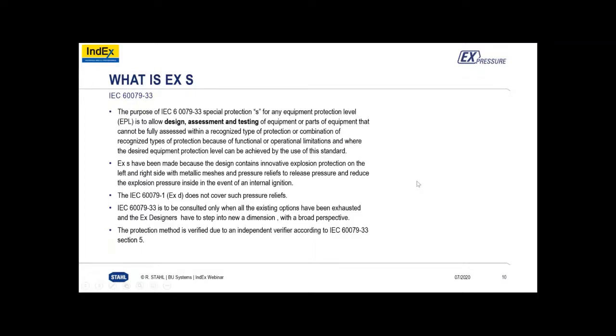So I'll go through this one. So gentlemen, EXS, you're wondering what EXS is. EXS is for equipment with an EPL, equipment protection level, that is designed, assessed, and tested for parts of equipment that can't be assessed within a recognized type of protection or a combination of different protection techniques because of functional or operational limits where the designed equipment protection level can be achieved by the use of this standard.